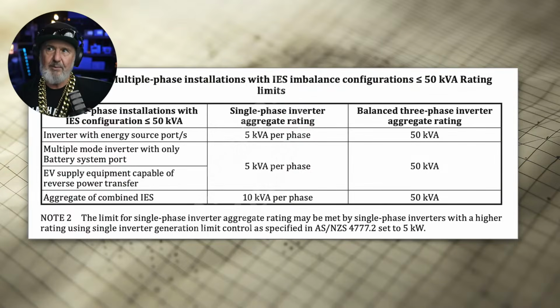If you have EV supply equipment capable of reverse power, it's also 5 kVA per phase. Now, this is a really odd one. Be careful here: people often say, I've got an EV charger. What they actually mean is they've got EV supply equipment on the wall, more technically known as EVSEs, which is an AC source that I connect to my vehicle, and my vehicle has an inverter inside it that converts that AC to DC to charge the battery. However, it is possible to have a bidirectional inverter in the vehicle. I don't know of any that have this, that can then export power back out from the battery, convert it to AC, and send it back to the supply equipment. Pretty odd, but there's a big problem.